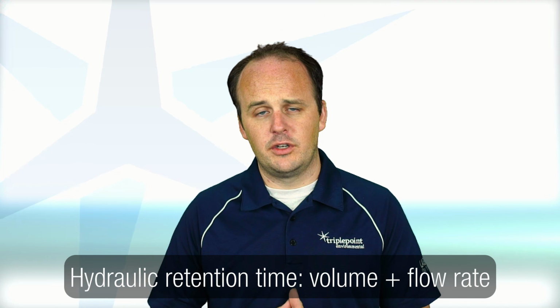The other thing that the lagoon volume and dimensions tell us is how deep the lagoon is. Lagoon depth is a very key parameter in that oxygen transfer efficiency equation. Generally speaking, the deeper the lagoon, the more oxygen transfer we can accomplish, very simply because the bubble has more time to rise through the water column and transfer oxygen to water the deeper the lagoon is. So we really need that.